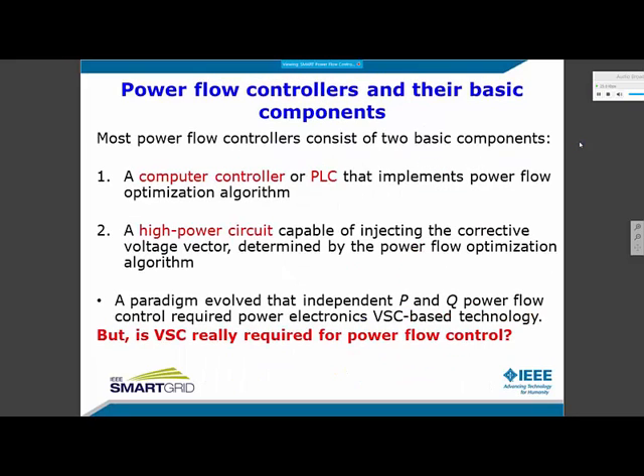Most power flow controllers consist of 2 basic components: a computer control or PLC, that implements the power flow control algorithm, and a high-power circuit capable of injecting the corrective voltage vector determined by the power flow control or optimization algorithm. Over the years, a paradigm evolved that independent PQ power flow control requires power electronics inverter technology. But is that really true? Let's examine further.